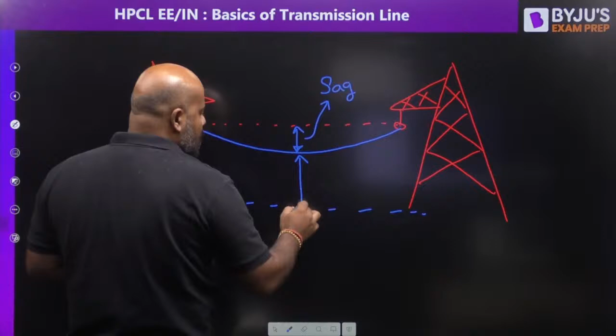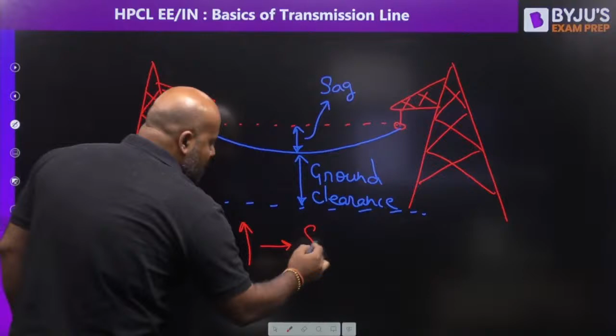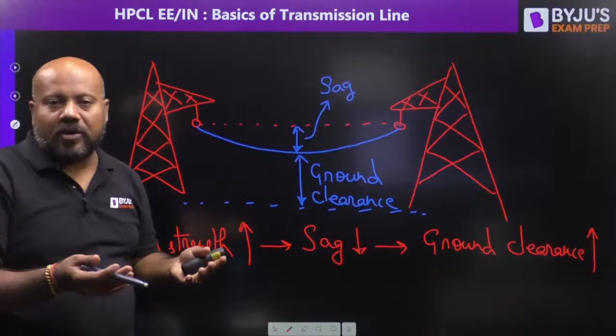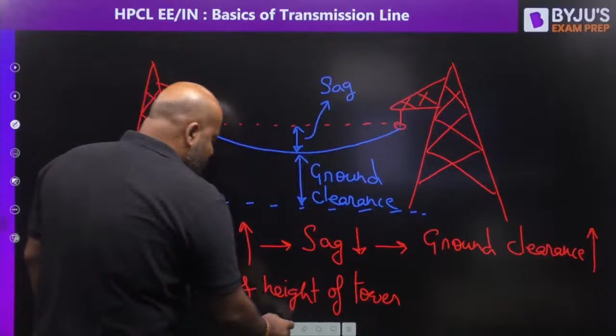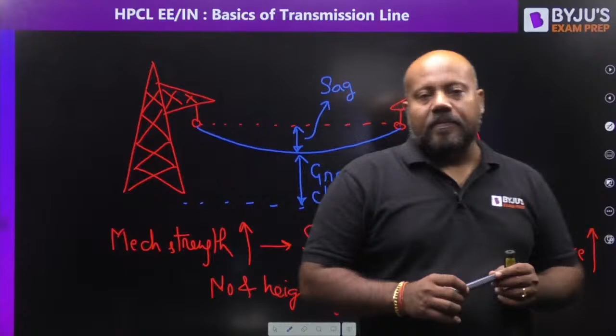Ground clearance. So what is happening? If mechanical strength is increased, then sag is going to be less. If sag is less, obviously the ground clearance is going to be more. If ground clearance is more, it means the height of the tower and the number of transmission towers is going to be less. So ultimately, the total cost of transmission is going to be comparatively less. Is it clear, everybody? Just tell me in the comment section. Are you able to follow this?